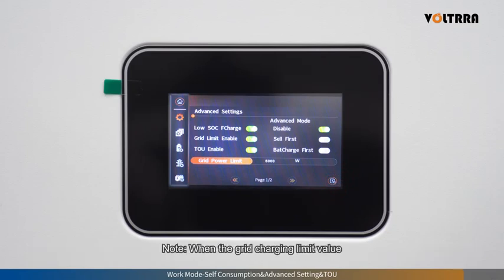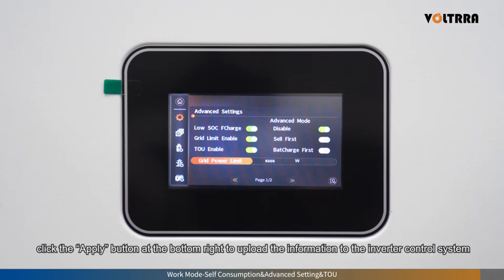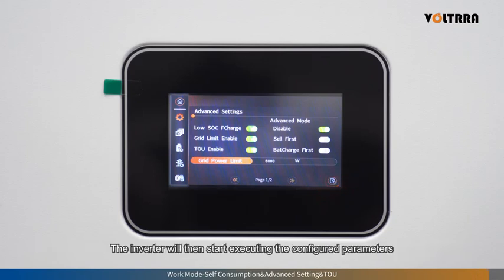Note: when the grid charging limit value and the TOU charging power value are inconsistent, the system will execute the smaller value by default. After completing the parameter settings of each page, click the Apply button at the bottom right to upload the information to the inverter control system. The inverter will then start executing the configured parameters.